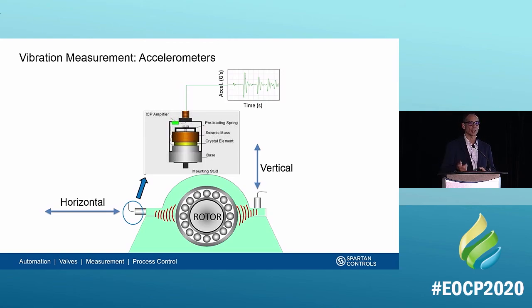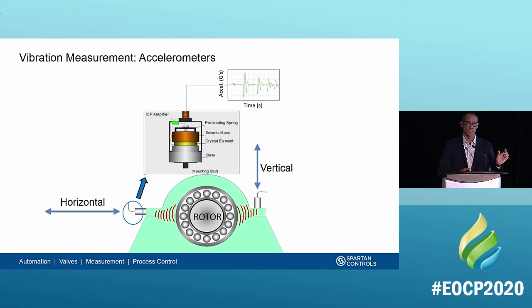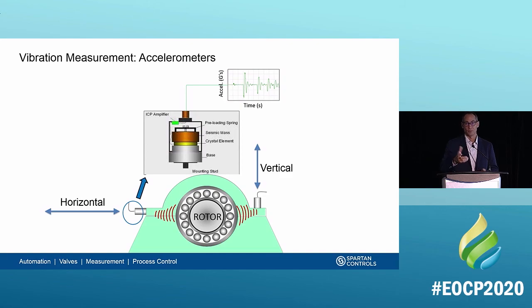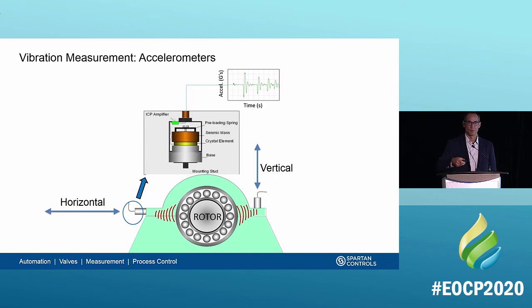To measure vibration, we use a piezoelectric crystal-based accelerometer installed directly onto the motor — for example, one mounted to measure horizontal vibration and one for vertical vibration. The piezoelectric crystal suspends a mass; as vibration increases, the crystal vibrates and produces an electrical signal. We take that electrical signal from the crystal into our signal conditioning and measuring device. The crystal allows us to convert physical vibration into an electrical signal that we can actually measure.